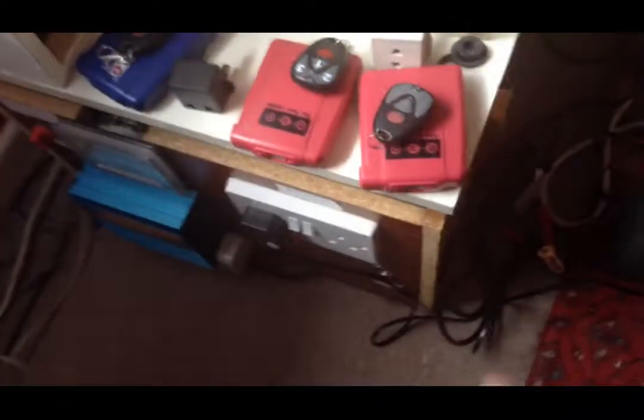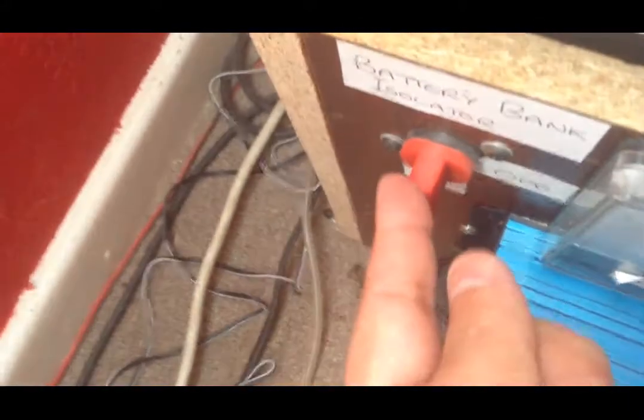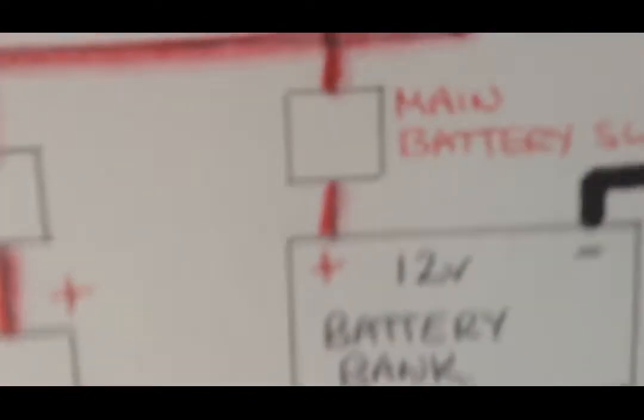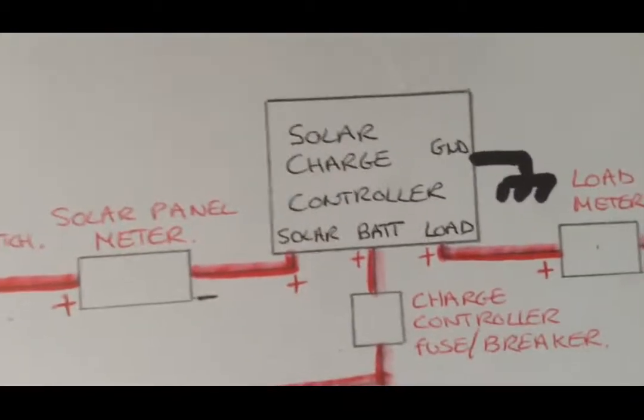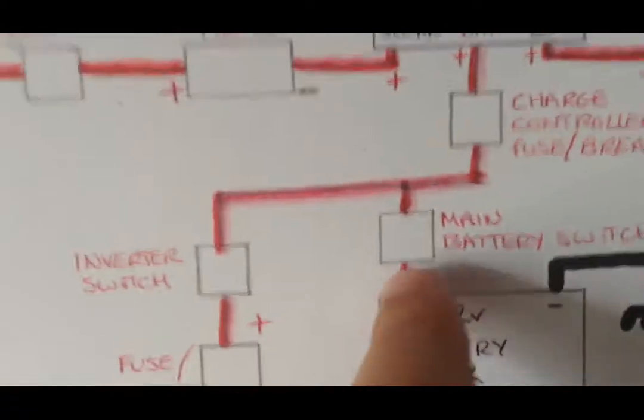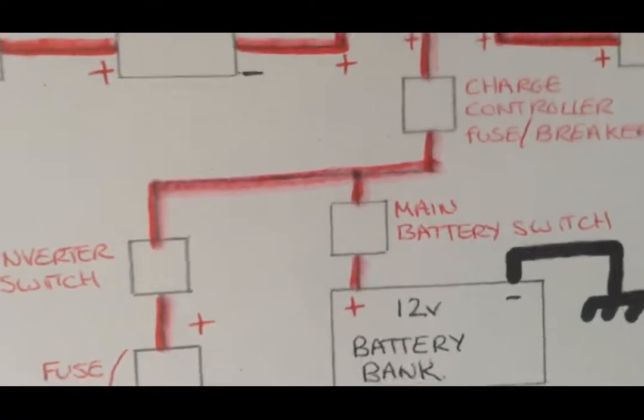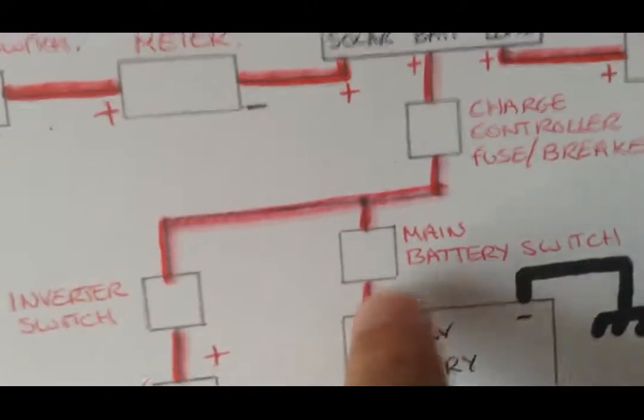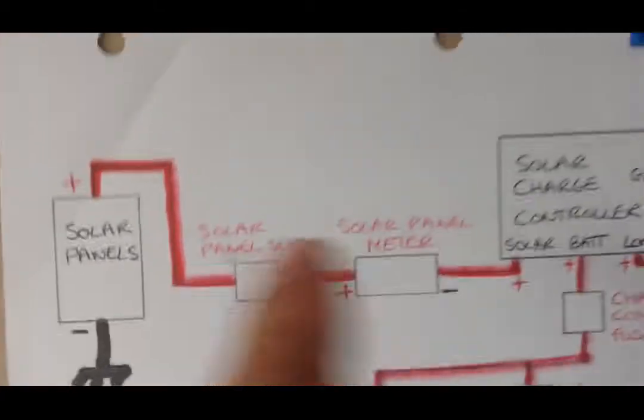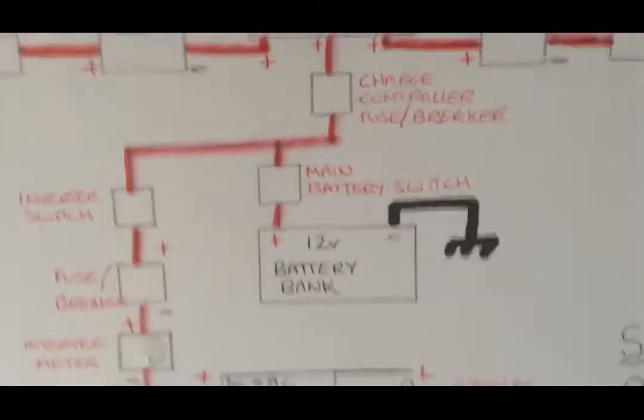The battery bank is inside this box, as you've seen before, and my main switch is here, about 2 or 3 inches from the positive of the battery bank. So if you have any electrical issue, you can cut off the battery bank by switching this off here. Safety thing this is. So basically, if you have any sort of problem, anything goes wrong, goes short, overheats, starts smoking or whatever, you can quickly disconnect the battery bank here. Or if you want to work anywhere on the system, you'll need to disconnect the battery bank and the solar panels before working on the system. So that is the battery bank.